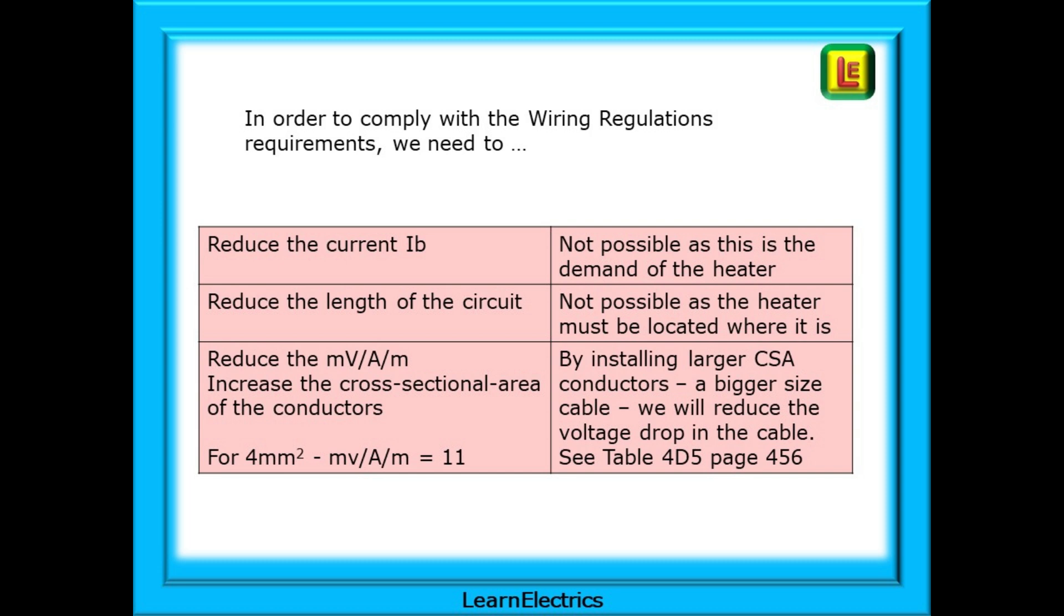We can say that this is unacceptable and we should reconsider our design options. In order to comply with the wiring regulations requirements we need to either reduce the current IB, but this is not possible as this is the current demand of the heater. Turn it on and it draws 20 amps of current. Can we reduce the length of the circuit? Not possible as the heater must be located where it is.